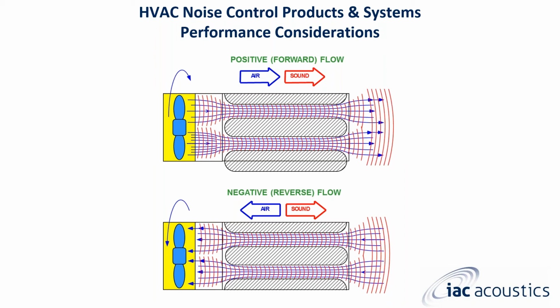Under forward flow conditions, high frequency sound is refracted into the duct silencer walls. With reverse, this is a condition that exists when sound waves and airflow are traveling in the opposite direction. Case in point, being pulled back through. Under reverse flow conditions, sound is refracted away from the walls, but yet toward the center of the duct silencer.